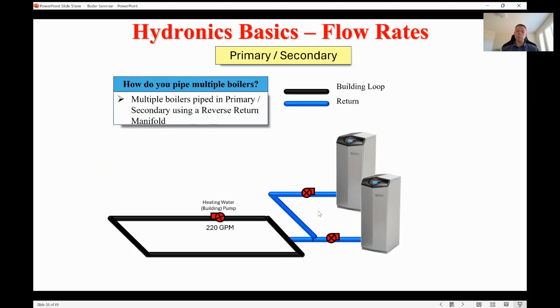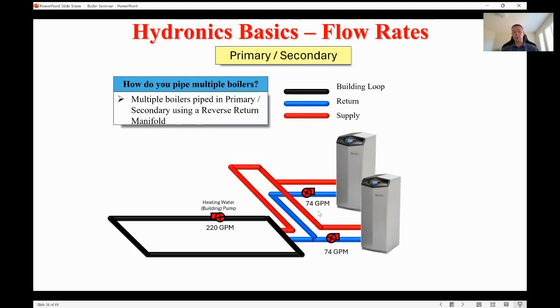So if you have multiple boilers, this is what your primary, secondary looks like. Generally, you have those 2 closely spaced T's. They're going to be done kind of like a manifold. So the inlet and outlet, maximum 12 inches or 4 pipe diameters apart. Your system loop is hydraulically decoupled from your boiler loop. If you take a look here, each boiler has its own pump size to give it exactly the flow rate it needs. The first one in is the last one out.